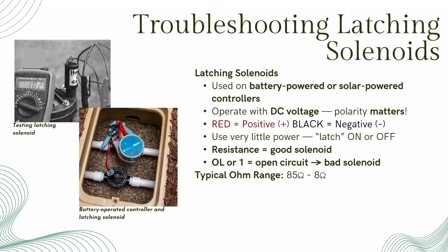Unlike standard AC solenoids, latching solenoids are used on battery or solar-powered controllers and operate using direct current, DC. They use a small pulse of current to latch the plunger in position, up for on, down for off, and then draw no additional power. Because DC circuits are polarity sensitive, the red meter lead must be on the positive wire and the black lead on the negative. If your multimeter shows any resistance, the solenoid is good. If it shows OL or 1, that solenoid has failed and needs replacement.